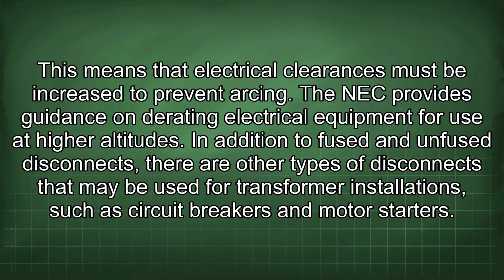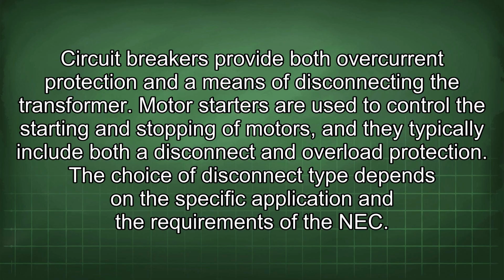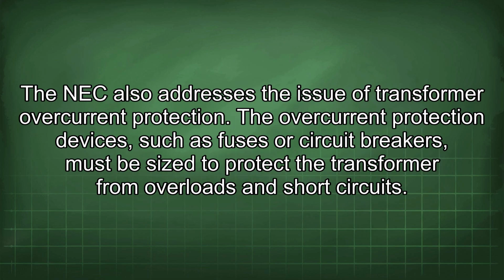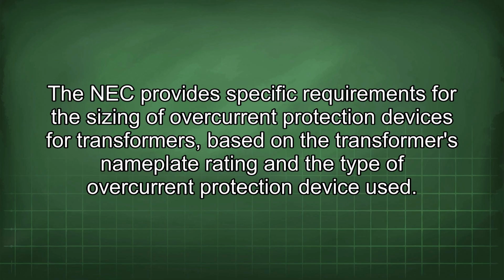In addition to fused and unfused disconnects, there are other types of disconnects that may be used for transformer installations, such as circuit breakers and motor starters. Circuit breakers provide both overcurrent protection and a means of disconnecting the transformer. Motor starters are used to control the starting and stopping of motors, and they typically include both a disconnect and overload protection. The choice of disconnect type depends on the specific application and the requirements of the NEC. The NEC also addresses the issue of transformer overcurrent protection. The overcurrent protection devices, such as fuses or circuit breakers, must be sized to protect the transformer from overloads and short circuits. The NEC provides specific requirements for the sizing of overcurrent protection devices for transformers, based on the transformer's nameplate rating and the type of overcurrent protection device used.